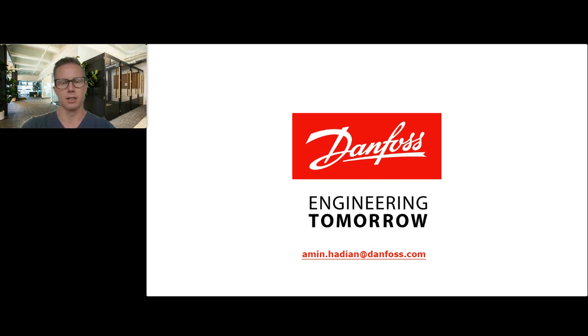So that's the standard. Then we have some, for instance, when we are overspeeding the pump, which I mentioned in my part of the presentation, to make it provide even more flow. In that case, we have a recommendation saying 500 hours in between service. 500 hours is usually more than enough when we're talking about firefighting systems. So it depends what mode you run the pump in.